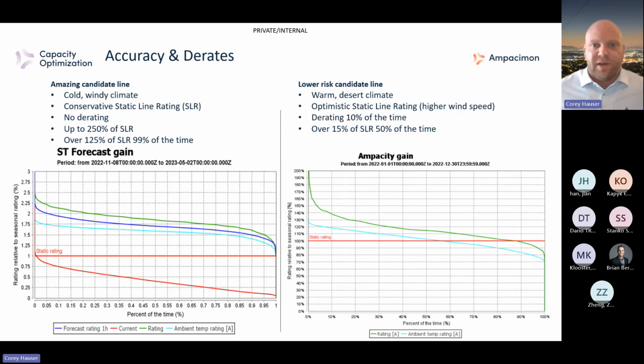Moving forward, let's compare a couple of lines. When discussing dynamic line rating, accuracy comes into play, along with the potential for derates, which do exist, to be honest, and you'll see an example where it occurs. The one on the left is pretty much the most ideal dynamic line rating scenario ever, in a Nordic climate that's cold and windy, starting with conservative static line ratings. It truly has no derates, with a 25% gain 99% of the time, up to a 250% gain at the lower percentage of time. It doesn't get more ideal than that, and it has everything going for it, starting with that conservative static line rating that allows you to capture more gains. But when discussing the potential for derates and being open about that, we noticed in the FERC ANOPR it wasn't something they seemed to want to talk about much.